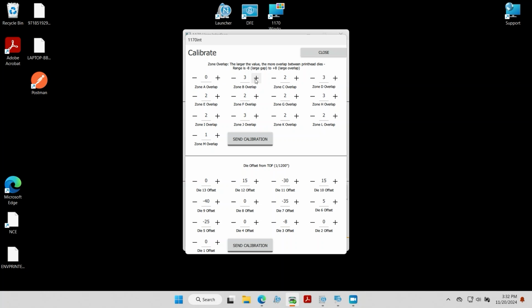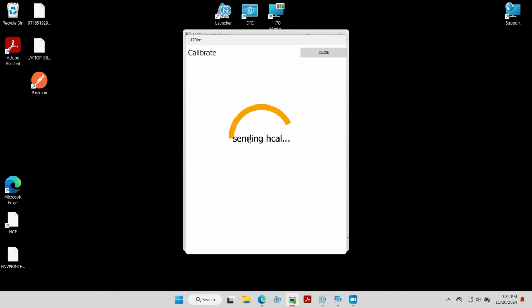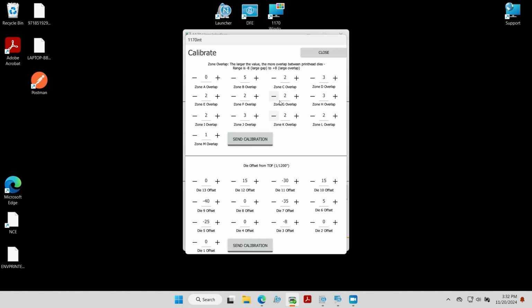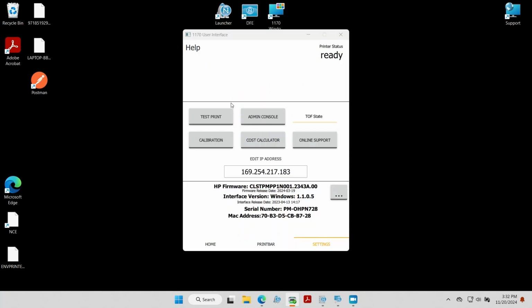To make a calibration change, press the plus or minus buttons to adjust the value of the die line you're correcting. We recommend changing by increments of 2 to begin with. Then press Send Calibration. Once calibration is sent, close this screen and do a test print.